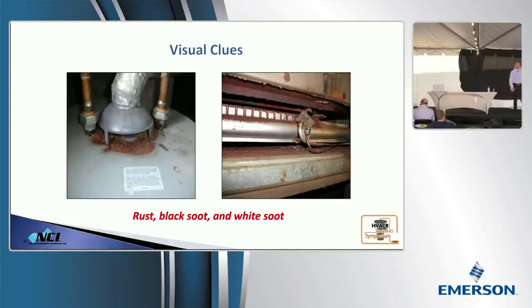Now, there's a couple of things it could be. It could be a combustion air problem. It could be a blocked flue. What's one of the number one restrictions in a blocked flue? Bird's nest, right? You guys see a lot of that? You guys have seen a house where the chimney isn't working. The only type of bird that should be in a chimney is a dead one laying in the bottom of it with a piece of straw in its mouth. That chimney's working. If you have a bird's nest in a chimney, the chimney doesn't work.